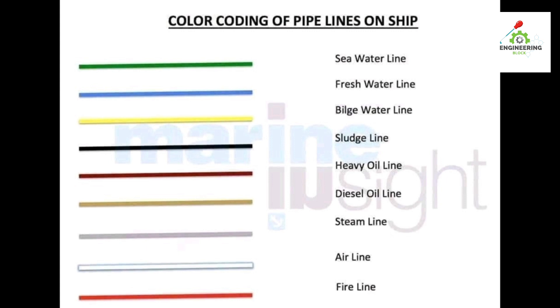On ships: green is used for the sea water line, blue is used for the fresh water line, yellow is used for the bilge water line, black is used for the sludge line, brown is used for the heavy oil line and diesel oil line, and white is used for the airline. The fire line is red.